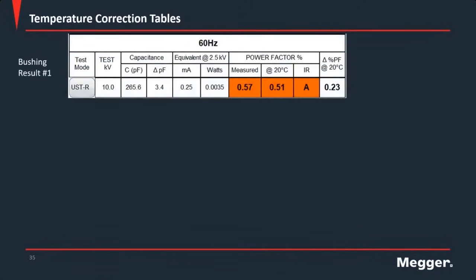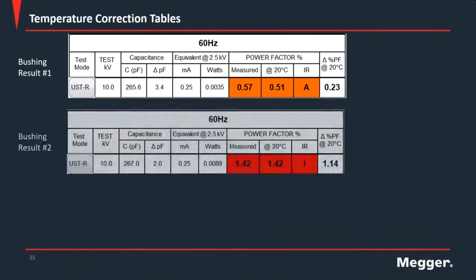So temperature correction tables, what I have here are a couple bushing results. The first test, we see that corrected to 20 degrees C, we have a value of 0.51. It has not changed too significantly, and yeah, it's a little aged from the nameplate values. But then the second bushing result, we see that the value at 20 degrees C is quite a bit higher, almost 3 times higher. The difference in power factor from 20 degrees C is quite a bit, and it's being recommended that this bushing be investigated.